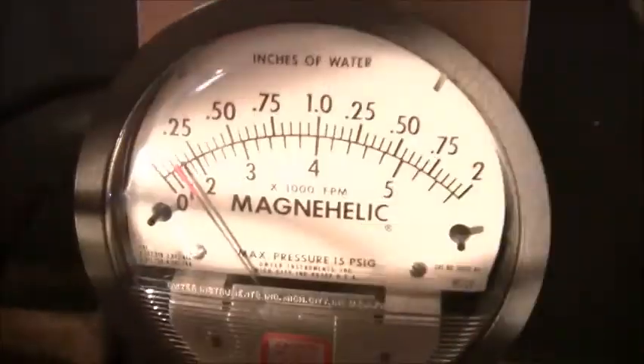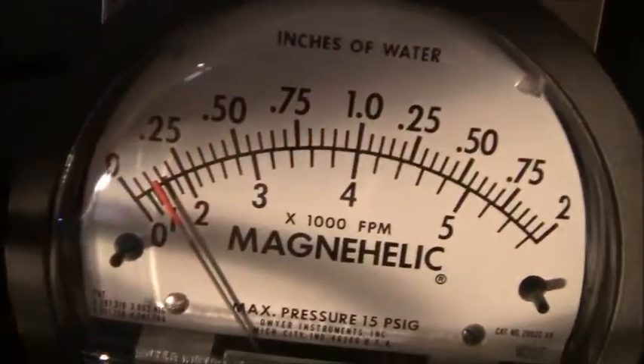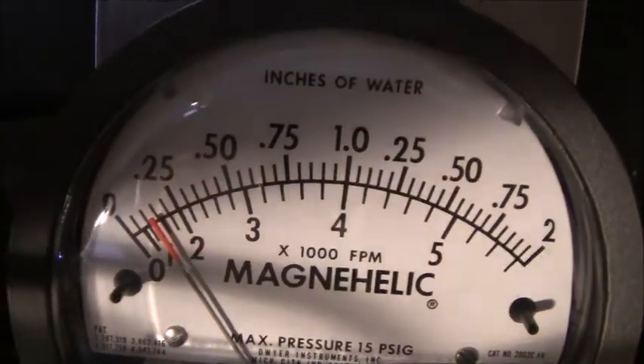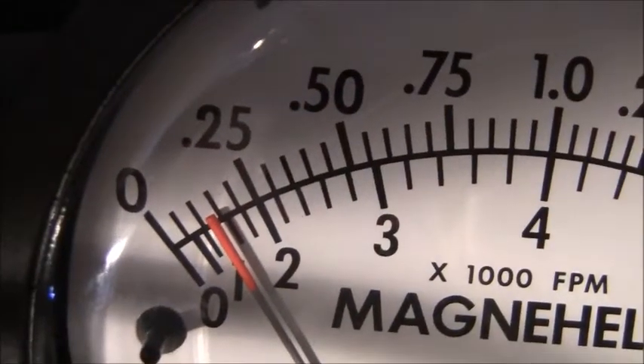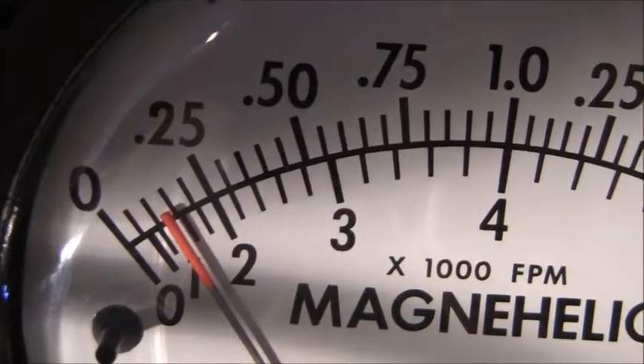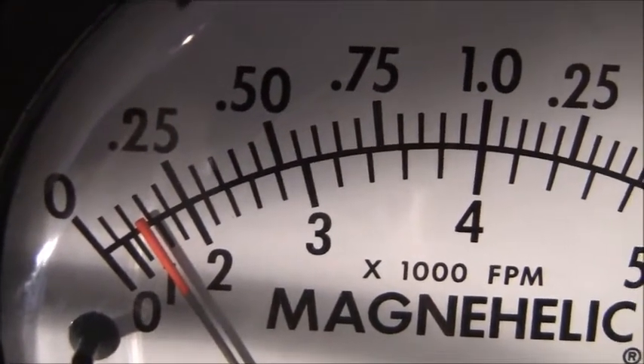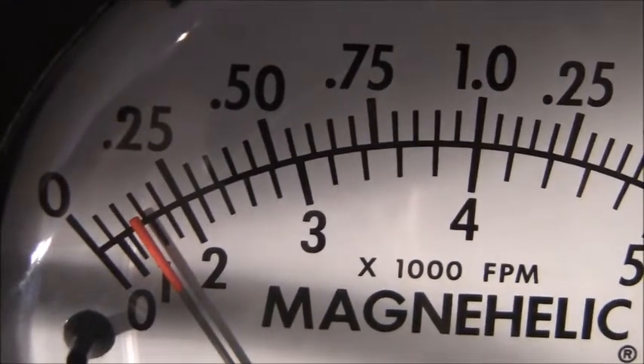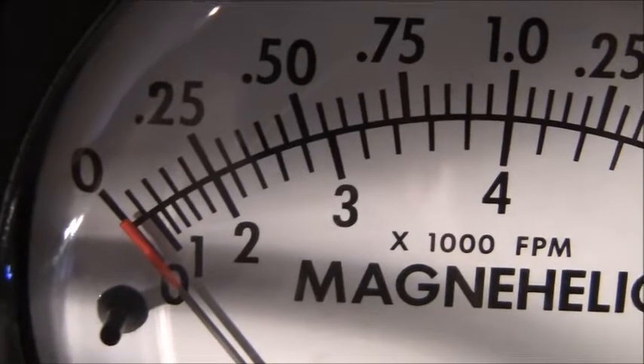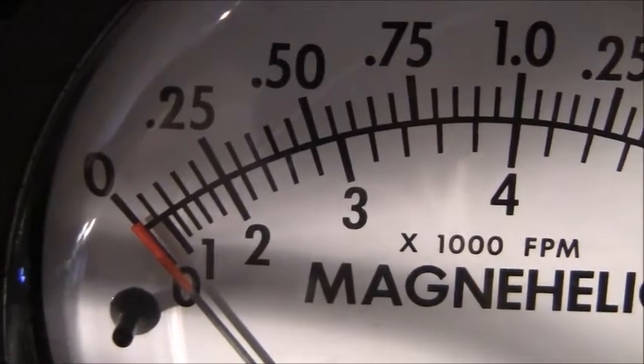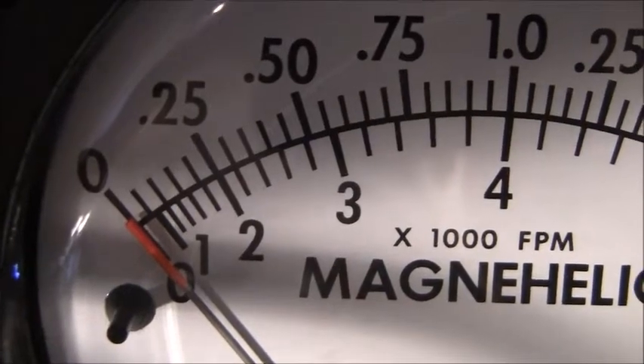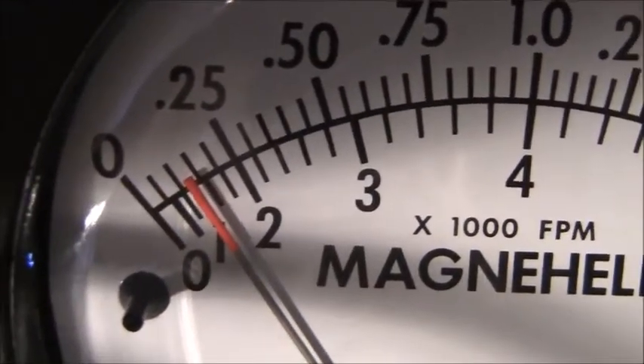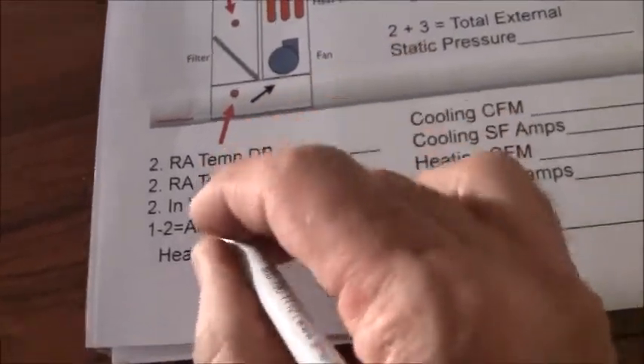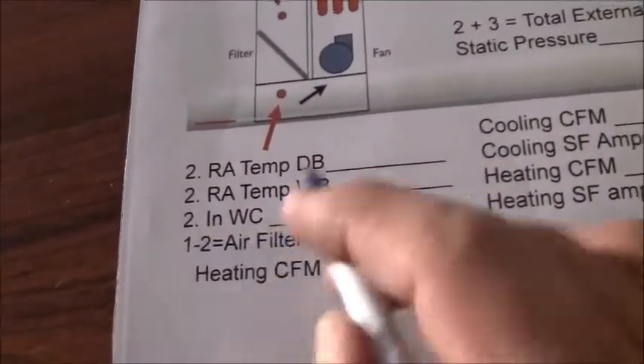Now there's the reading on the Magnehelic gauge after the filter, before the fan. That number is 0.125. I'm going to pull it out and then put it back in just to show you the needle movement, if I can find that opening. There it is. 0.125. So let's go ahead and write that down. That number is this one right here, this number 2 reading.